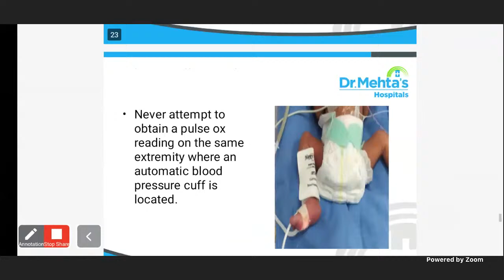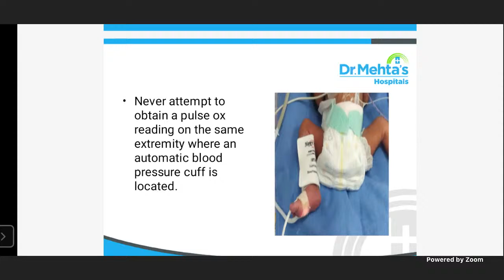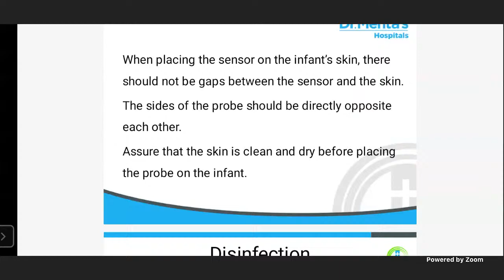Sorry for the inconvenience. Never attempt to obtain a pulse oximeter reading on the same extremity as the BP cuff. If you are connecting the BP cable on a hand or foot, you are not supposed to check the pulse oximeter on the same hand or foot, because it will not give correct saturations. Again the same point is coming: there should not be a gap between the sensor and skin, the sides should be directly opposite to each other, and the skin should be clean and dry before placing.